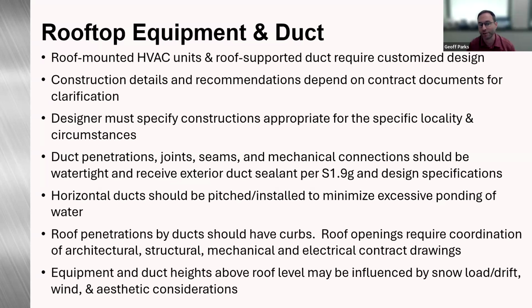So the designer must specify constructions that are appropriate for the specific locality and circumstances. Again, depending on the location for snow load, rain load, not rain load, but rain intensity, ice, that needs to be taken into account when designing for rooftop ductwork, especially. Any duct penetrations, joints, seams, mechanical connections should be watertight. Receive exterior duct sealant per S 1.9G, and any specifications that are specific for that project.